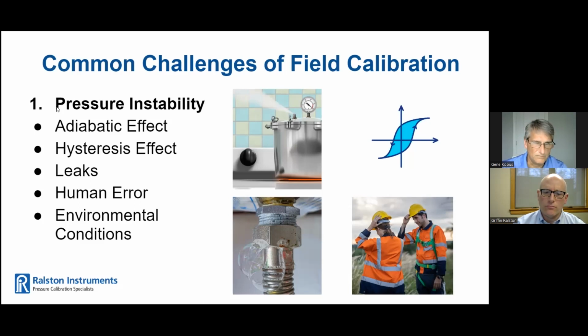And of course, human error: inconsistent pumping speed, improper handling of controls, incorrect reading of pressure gauges, and poorly trained users who fail to correctly understand the adiabatic effect. So if they don't wait for the system to come to equilibrium, or don't effectively prime the pump, there's a lot of trapped air in the system, which would cause you to have instability.